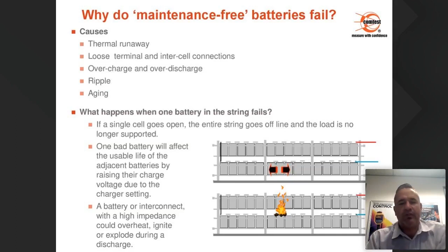A battery or interconnect with a high impedance could overheat, ignite, or explode during a discharge. So let's say the power's gone off and we're drawing power from our batteries under load. These links or straps in between the battery cells that join them could fail and ignite and cause a fire. So we have fire hazards with batteries as well.